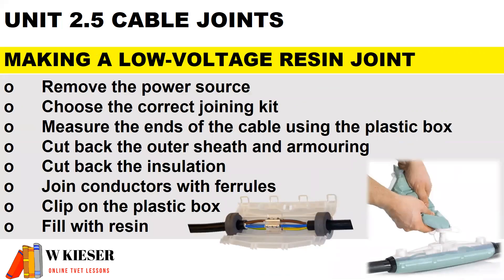When making a low voltage resin joint, also known as a Scotchcast type joint: first remove all power sources. Choose the correct joining kit, like a Scotchcast joint kit. Measure the ends of the cable using the plastic box. Cut back the outer sheath and armoring. Cut back the insulation. Join conductors with ferrules. Clip on the plastic box and fill it with resin.